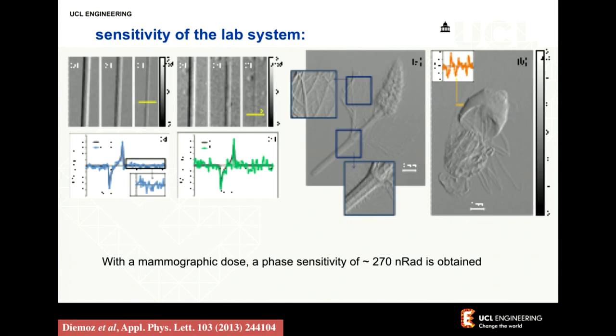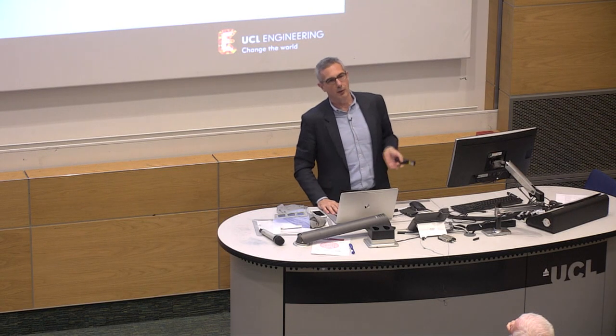Now you have two images: the phase image and the attenuation image. The phase image for us is a map of the refraction angles caused by every part of the specimen. Once you have that, you can try to understand what's the minimum refraction angle that you can detect. In the lab, constrained to a dose which is about a mammographic dose, we measure about 250 nano-radians — a quarter of the micro-radian I mentioned before. That's the angle subtended by a quarter of a millimeter placed a kilometer away, resolved here at UCL. If you go to a synchrotron you can do much better, but then you have to spend several hundred million pounds.